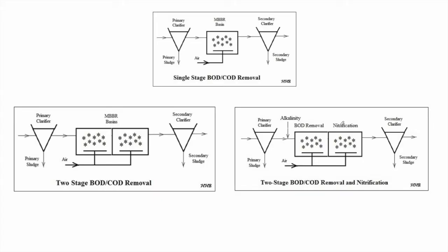Depending on the type and degree of removal of pollutants, we can have many MBBR stages. For a single stage BOD/COD removal, we have one aerated MBBR basin with a primary clarifier upstream. The MBBR basin is always followed by a secondary clarifier where activated sludge settles. Unlike the activated sludge process, this sludge is not pumped back to the MBBR basin — it is simply wasted.